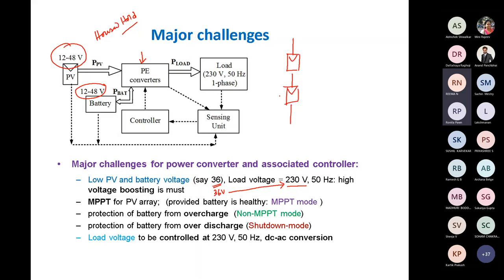if I use a high voltage system for solar, I have to connect so many modules in series. Typically in the market, the maximum voltage with which these modules are available is around 36 volt MPP. Later on I'll show you that if I use an inverter, because finally you need a DC to AC converter to cater to AC load - since solar and battery are DC - for an inverter, if you want 230 volt output, the DC bus voltage requirement is around 380 to 400. So just see how many modules you need to connect in series - it is more than 10.